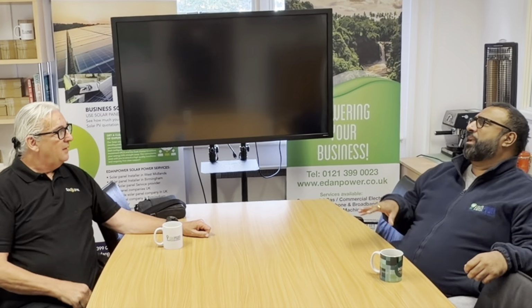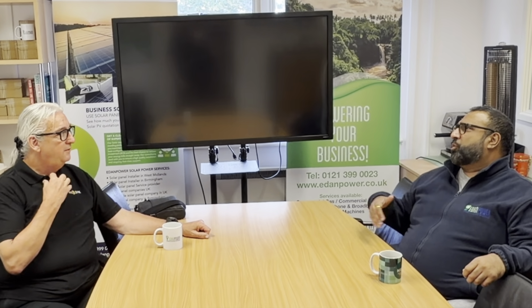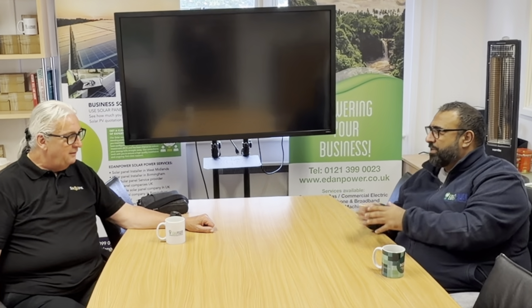So you don't need a gateway. Because the way that gateways operate, at the end of the day, let's say you've got 20 kilowatts of storage, the gateway is only going to be effective up to the 20 kilowatts. Is that right? Because all the energy's gone. So we are better off probably having lifeline supply on the inverter. So basically, you're limited to obviously your battery - what you're going to use.